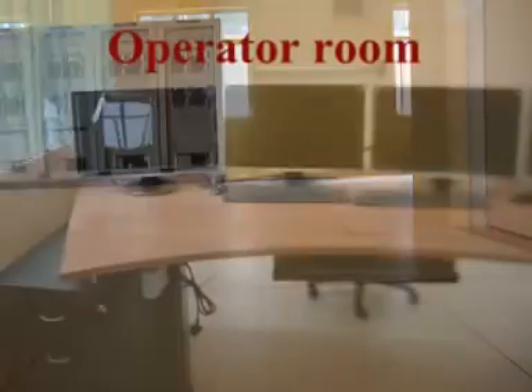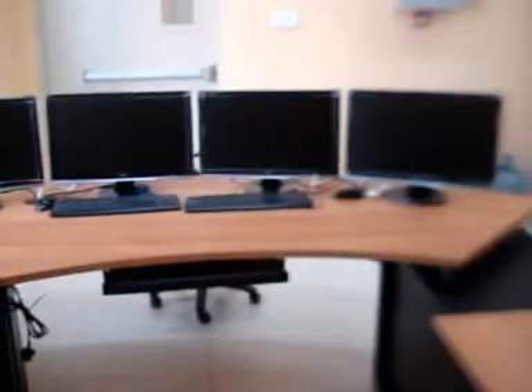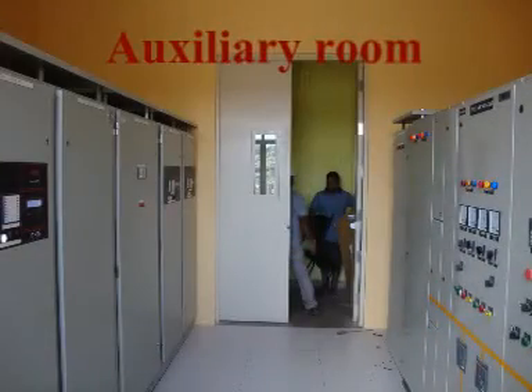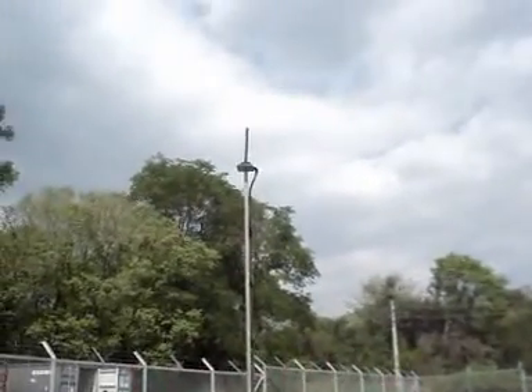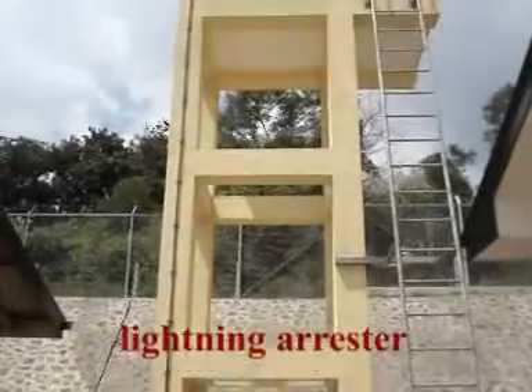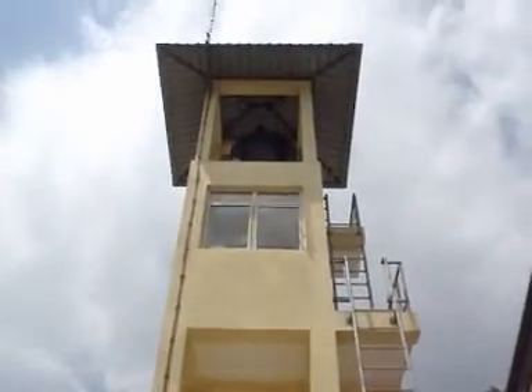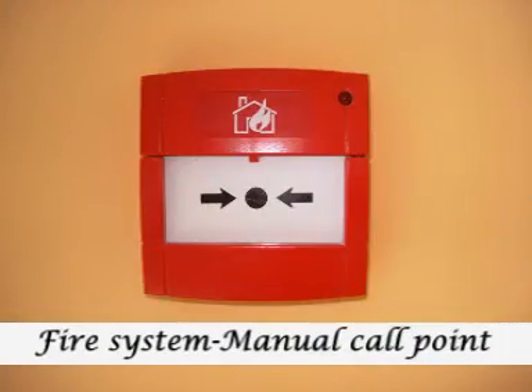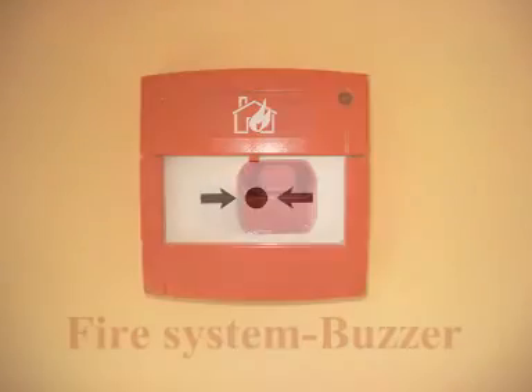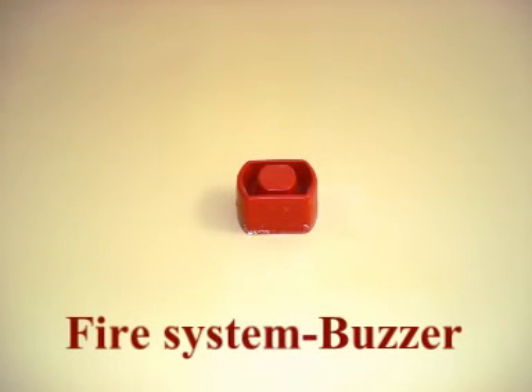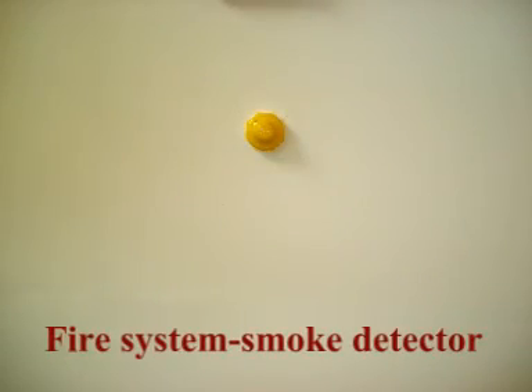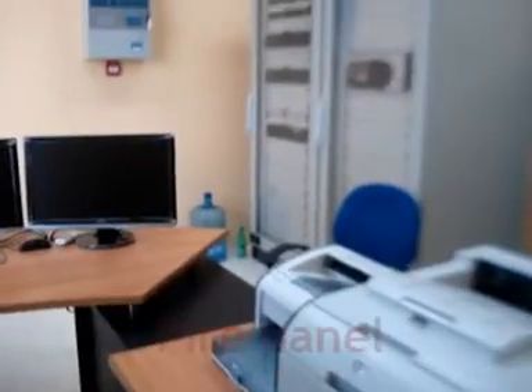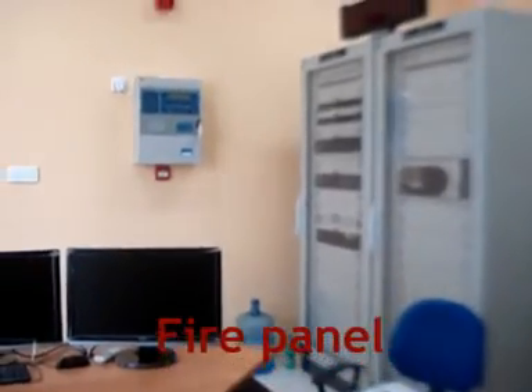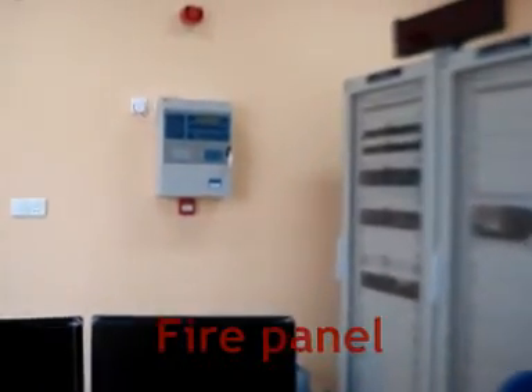Raised floor tiles are laid in the control and protection panel room, auxiliary room and operator room. A lightning rod system is introduced to protect the entire control building from lightning strikes. A fire detection system is commissioned inside the building and connected to the substation automation system to give a common alarm to the operator. The fire panel was fixed in front of the operator's desk so that the operator can attend to the panel quickly and find the fire zone.